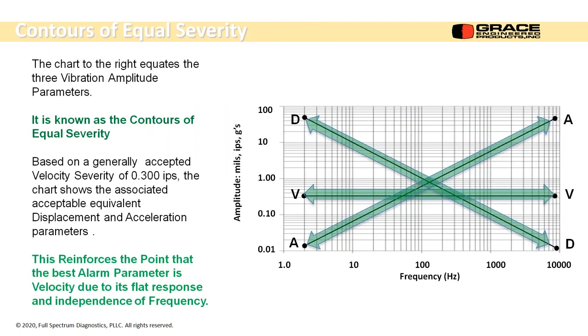Which brings me to the chart that kind of sums it up. This is what's called a contours of equal severity chart. Okay? We show velocity, we show relative displacement to that velocity, and we show relative acceleration to that velocity. We can choose any parameter we want, but when it all comes down to it, if I have a point that's right there that's 10 mils, I have to know what frequency it is. And if it's at 10 hertz, then I can calculate an equivalent velocity and see if I'm above or below that line. Okay.